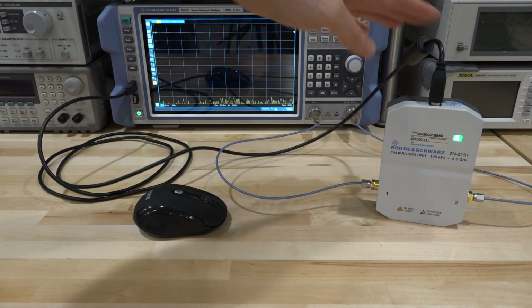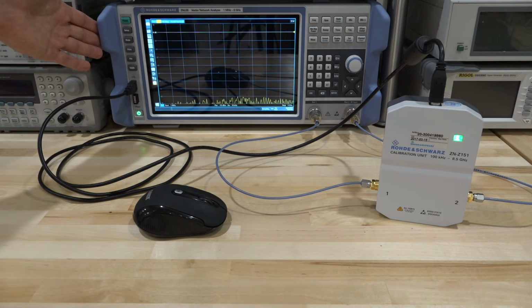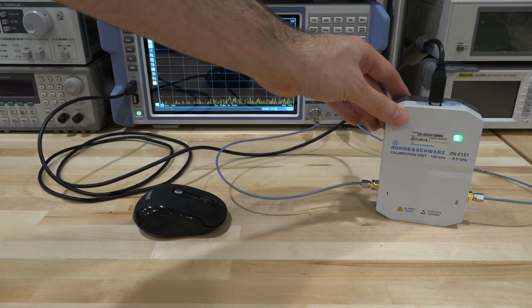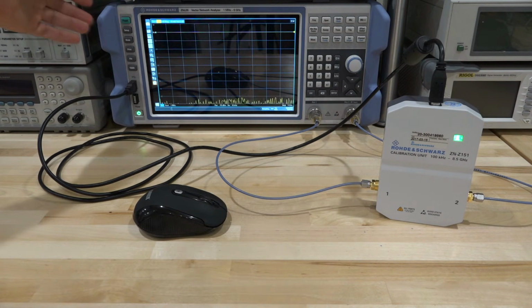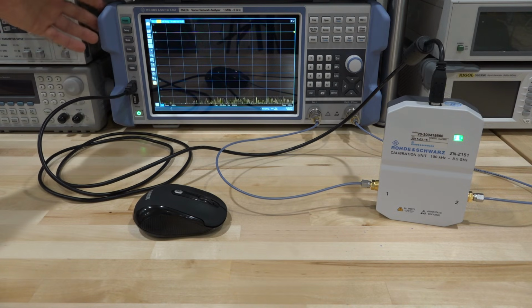Now, as soon as you connect this to the unit, the unit will download all the calibration coefficients, is aware of exactly which model you're using, and takes all the data, downloads it into the unit, and when you do a calibration, it will take all of that into account. This is similar to, let's say, the Keysight's eCal modules, works in a similar way. It's exceptionally fast and very reliable.